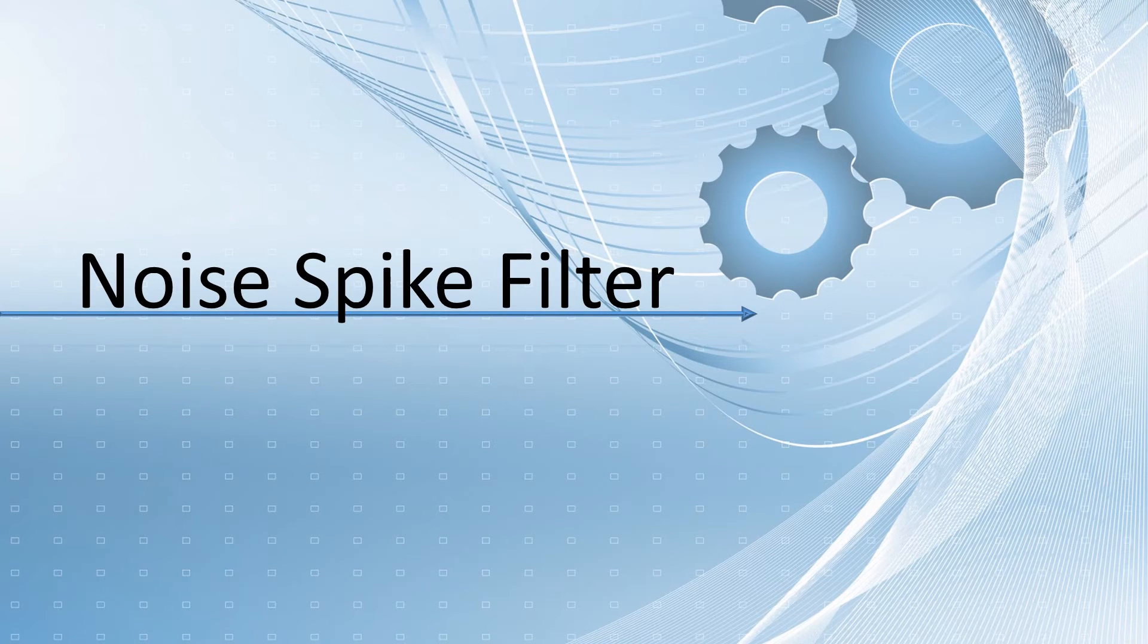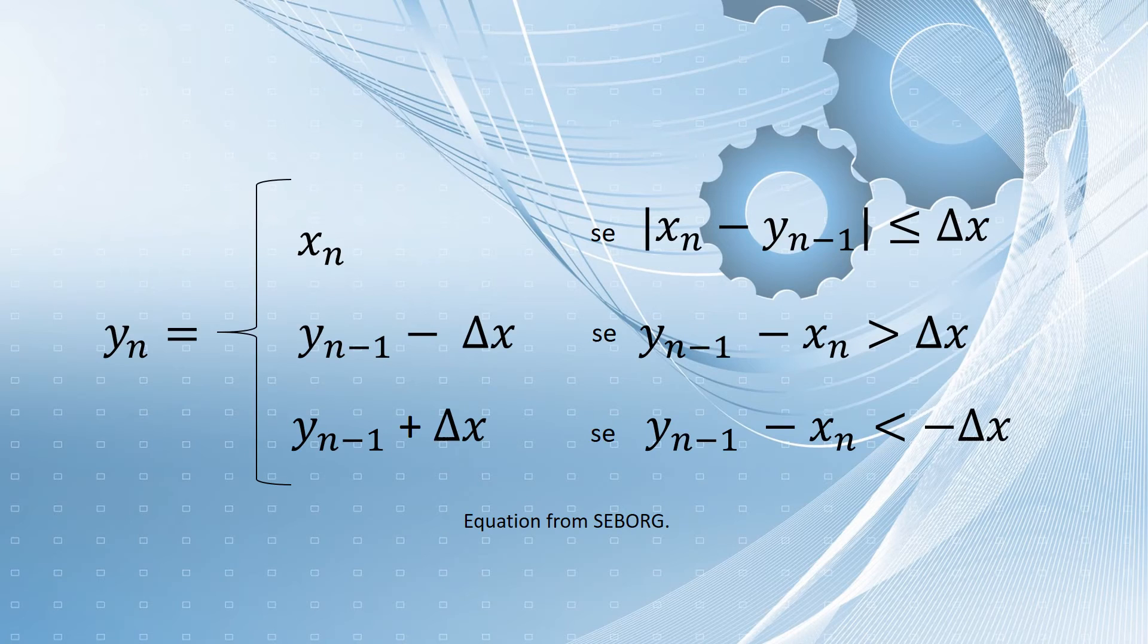If a noise measurement changes suddenly by a large amount and then returns to the original value at the next sampling instant, a noise spike is said to occur. To avoid that, the noise spike filter is used. Noise spike filters are used to limit how much the filtered output is permitted to change from one sampling instant to the next. If delta x denotes the maximum allowable change, the noise spike filter can be written as the equation shown.